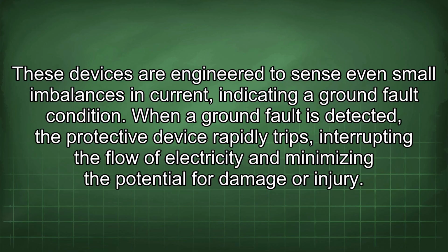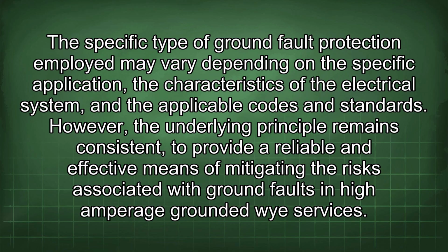When a ground fault is detected, the protective device rapidly trips, interrupting the flow of electricity and minimizing the potential for damage or injury. The specific type of ground fault protection employed may vary depending on the specific application, the characteristics of the electrical system, and the applicable codes and standards. However, the underlying principle remains consistent: to provide a reliable and effective means of mitigating the risks associated with ground faults in high amperage grounded Wye services.